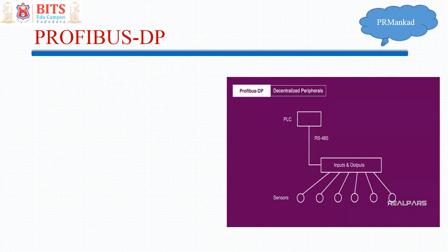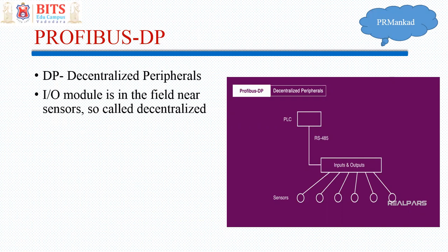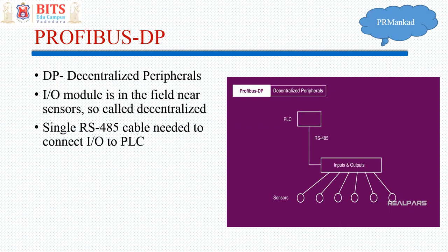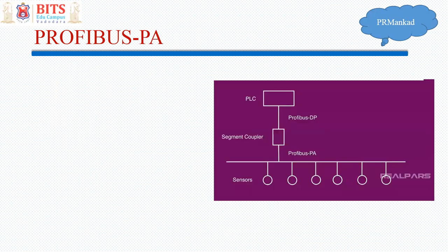Profibus DP stands for Decentralized Peripherals. Here, all the I/O modules that were previously connected near the PLC are moved to the field, and all sensors are connected to the I/O module. A single RS-485 link runs from the field to the central PLC. The devices or peripherals are thus decentralized — hence it is called Decentralized Peripherals. The I/O module is in the field near the sensors, and a single RS-485 cable connects it to the PLC.